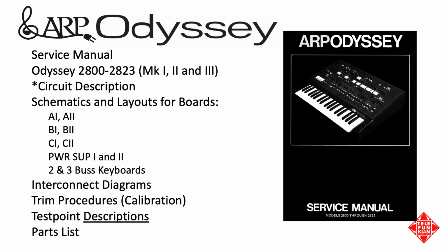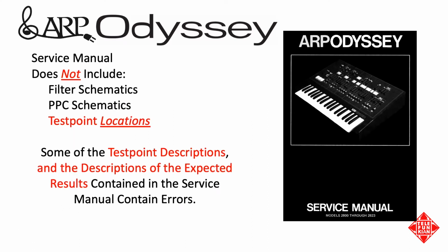The versions available online are old scans with very low resolution, making the schematics and the PCB layouts very difficult to read. In addition, the service manual does not include any filter schematics or the schematic for the PPC control, and most importantly, the manual does not describe the specific location of the individual test points. Some of the test point descriptions and the descriptions of the expected results that one would obtain evaluating the various test points are also described in error. There are also errors on the PCBs that actually have deigned to include test point locations on them, such as PCB C2, which doesn't match up with a description of the test points in the service manual.